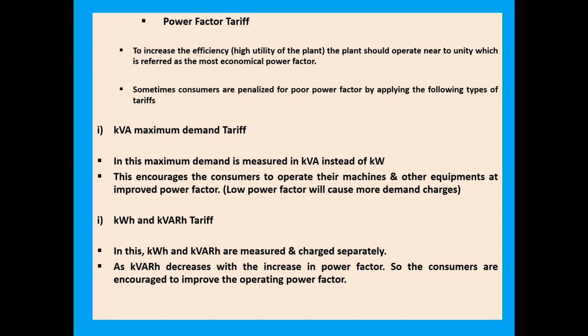First is the kVA maximum demand tariff, where maximum demand is measured in kVA instead of kilowatt, since kilowatt is VI cos phi. This encourages consumers to operate their machines and equipment at an improved power factor, since a low power factor causes higher demand charges. Consumers should be aware of this.